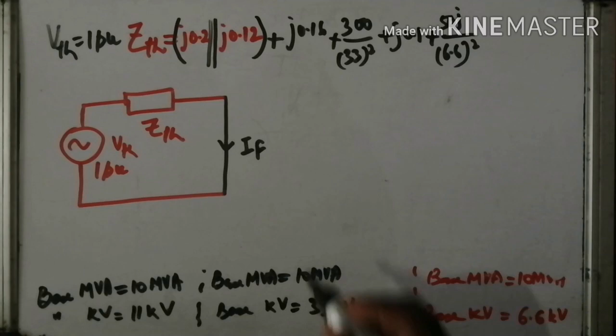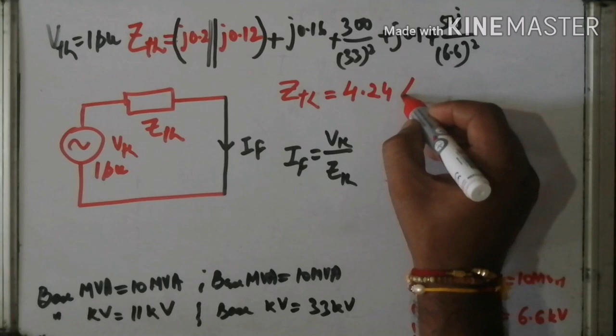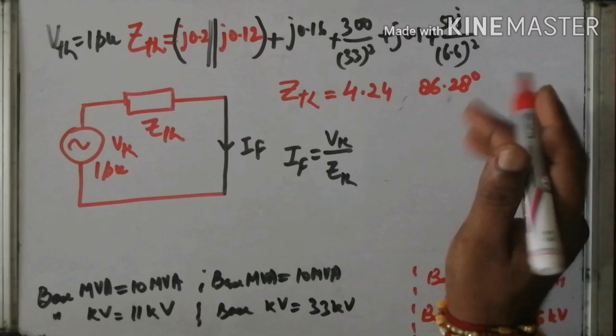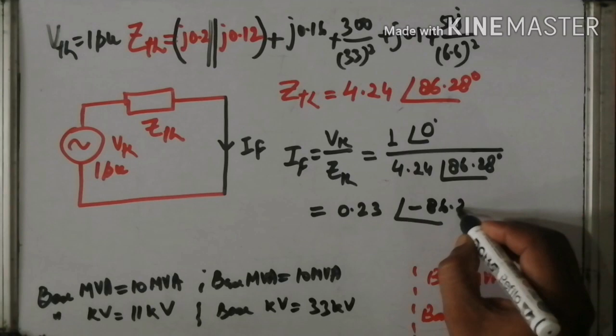After the calculation, the value of ZTH is 4.24 angle 86.28 degree. After the calculation, this one is the value of Z. Okay, that's why the fault current is given by the formula VTH divided by ZTH. What is the value of VTH? It is 1 per unit, so it is 1 angle 0 divided by this one, that is 4.24 angle 86.28 degree. After the calculation, it is 0.23 angle minus 86.28 degree. This is the value of current.